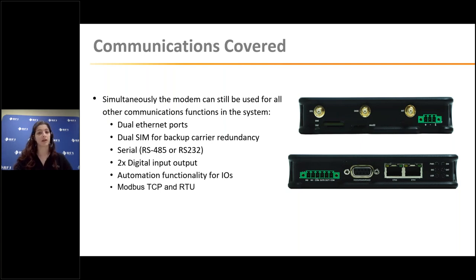They're able to provide that internet backhaul, so they're all cellular modems with generally upwards of Cat 4, providing that high speed. They're able to handle everything on your site basically. We've got dual Ethernet ports, so you could put two direct TriStars or EMCs directly into that modem, or have it connected to another PC or another Ethernet asset on that site. So you could potentially use it not just for running your solar system, but also for another Ethernet Modbus or Ethernet application on that site.